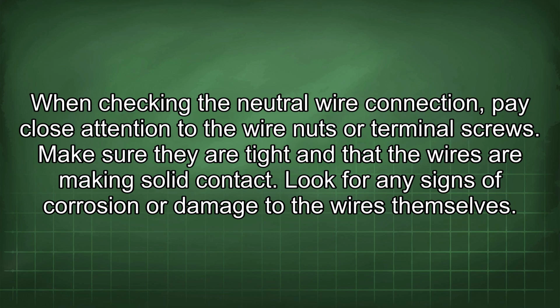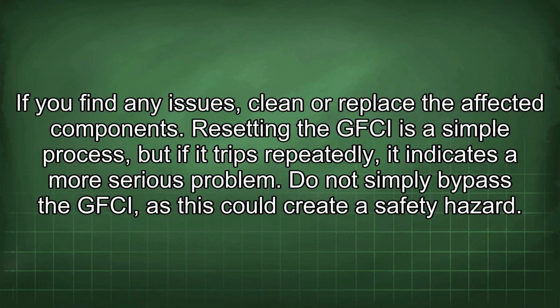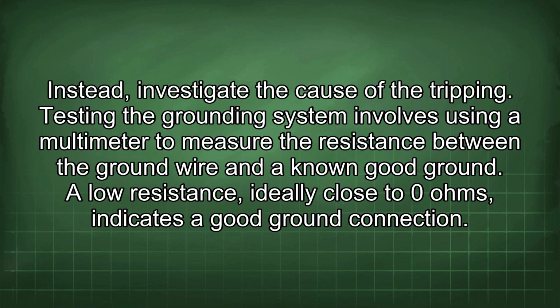When checking the neutral wire connection, pay close attention to the wire nuts or terminal screws. Make sure they're tight and that the wires are making solid contact. Look for any signs of corrosion or damage to the wires themselves. If you find any issues, clean or replace the affected components. Resetting the GFCI is a simple process, but if it trips repeatedly, it indicates a more serious problem. Do not simply bypass the GFCI, as this could create a safety hazard. Instead, investigate the cause of the tripping.